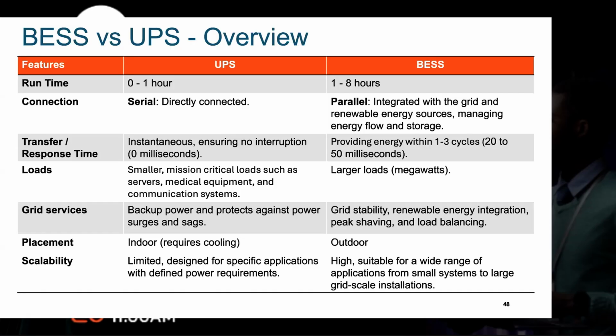The transfer time for UPS is instantaneous, ensuring no interruption, 0 milliseconds. But for the BESS, it provides energy within 1 to 3 cycles, 20 to 50 milliseconds, still very minute.